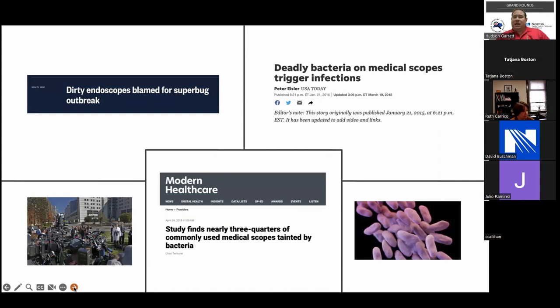Unfortunately, what we found is that with all of these devices, not only do we have device design issues, but we have tons of reprocessing failures. Those reprocessing failures, despite the best intentions of the reprocessing team, lead to contamination, right? And that contamination can then unfortunately translate to patient harm, or in some cases, unfortunately, patient death.